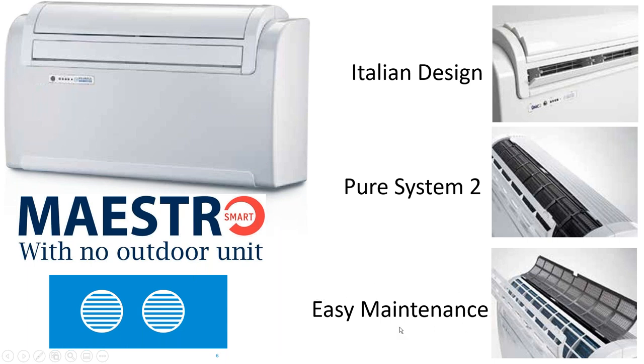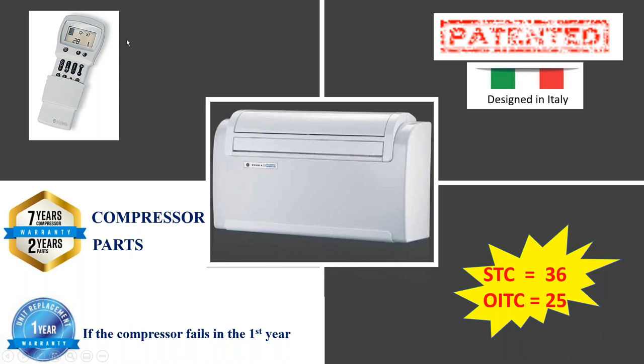The maintenance is quite easy because all you have to do is clean the filter, and then once a year, you should have the unit serviced where the coil gets cleaned and the drain pan gets cleaned. But on a regular, like a consumer level maintenance, it's just opening that flap and removing the filter or filters if you choose to use all of them. So upper left hand corner here, you see the remote control that ships with each unit. And the remote control is in Fahrenheit only in this brand, in the Smart. So if you had a customer that insisted on having a Celsius remote, if you will, or a remote that displays in Celsius, that's an accessory that can be ordered, okay?